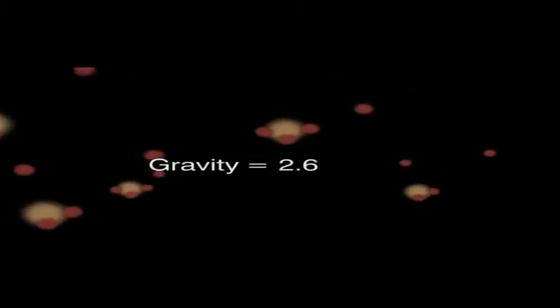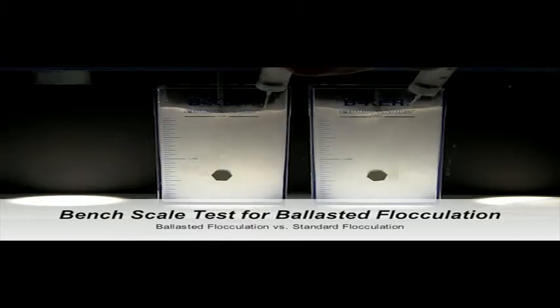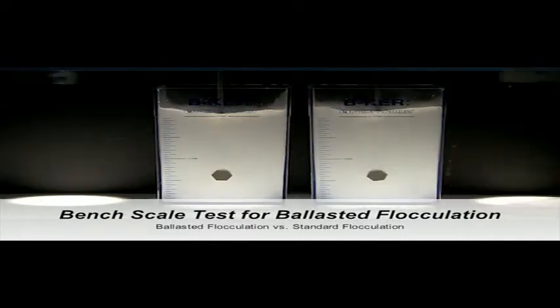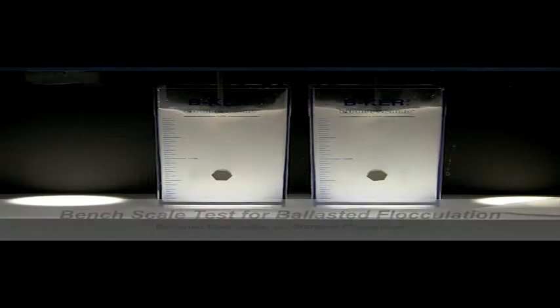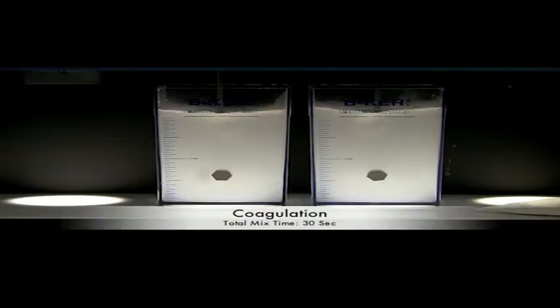The microsand has a specific gravity of 2.6 and is mixed with the polymer and coagulated solids to form a dense ballasted flock. This bench test shows two identical test samples containing raw water of 150 NTU turbidity. Both samples were treated with the same dose of chemical coagulant and polymer.